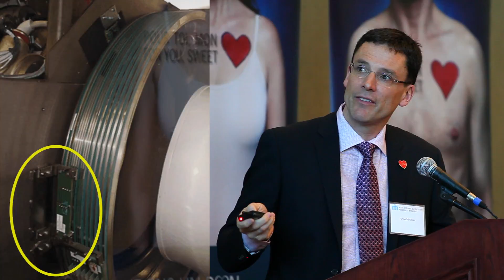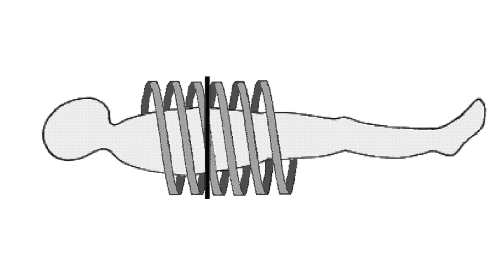And what it allowed the scanner to do is to keep moving. This portion here, this is where the non-moving part of the scanner connects to the moving part. And the connection was with these brushes that were developed. The brushes allowed the current to constantly pass from the ring to the non-moving part of the scanner. So the scanner could just turn and turn and turn as much as needed. So rather than taking a slice, what they could do, where the scanner would be the black line, is to gradually move the patient through the scanner and acquire a volume of information. And as the scanner is turning, it looks pretty much like a helix or a spiral. So if you compare that to, say, this spiral staircase, this is where we had the development with Dr.